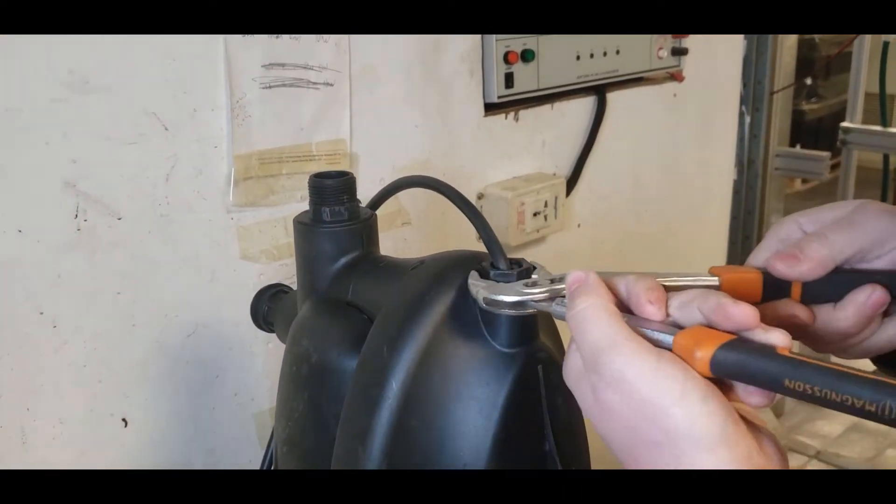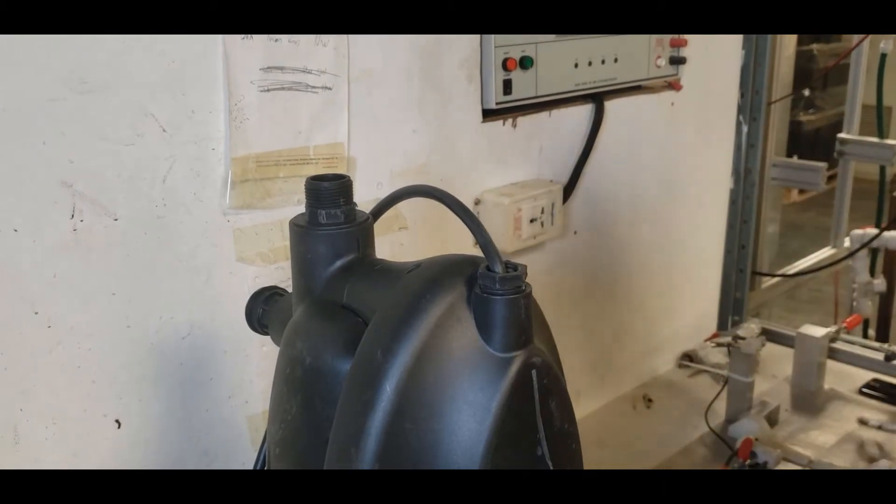Turn the pump off and isolate it from the source. Loosen the gland bolt to give the power cable some slack so it won't become damaged when removing the cover.